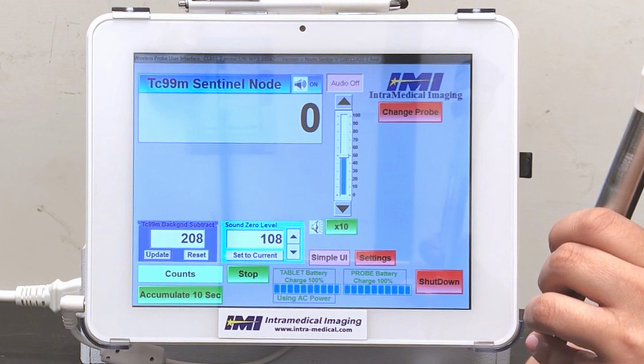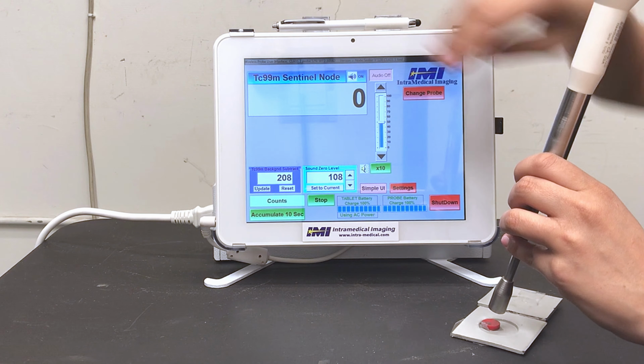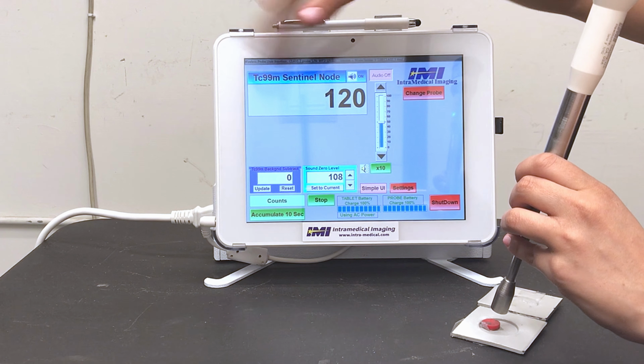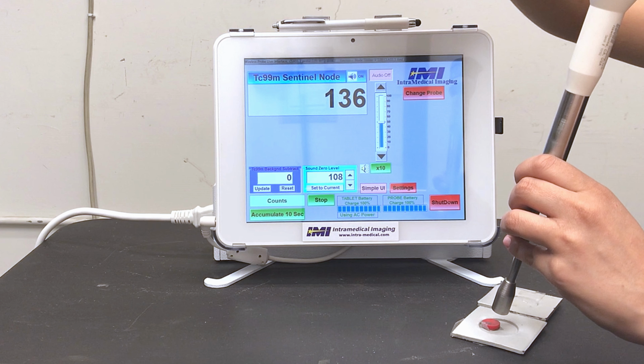The counts recorded in that main TC99 window will be the counts of the target lesion subtracted from the recorded background number in the smaller window. Circulators may record the background count subtract number as well as the highest count on the suspect lesion. To stop doing a background count subtract, select Reset in the small window, and the subtracted counts will then appear back on the main window.